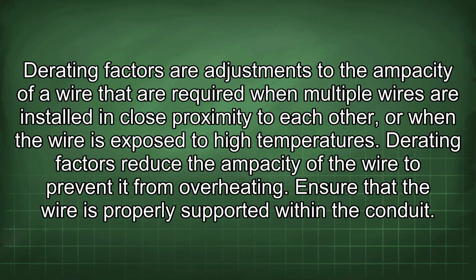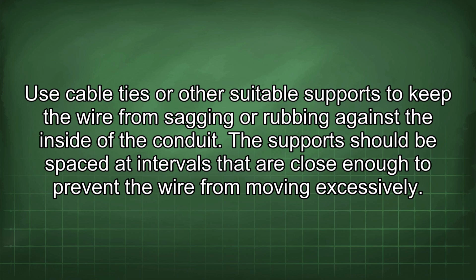Ensure that the wire is properly supported within the conduit. Use cable ties or other suitable supports to keep the wire from sagging or rubbing against the inside of the conduit. The support should be spaced at intervals that are close enough to prevent the wire from moving excessively.